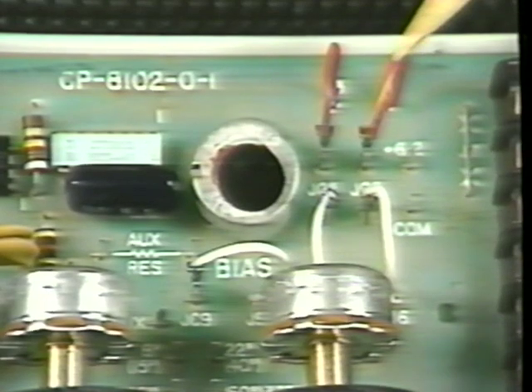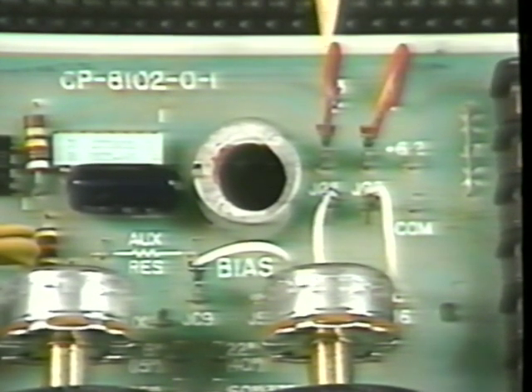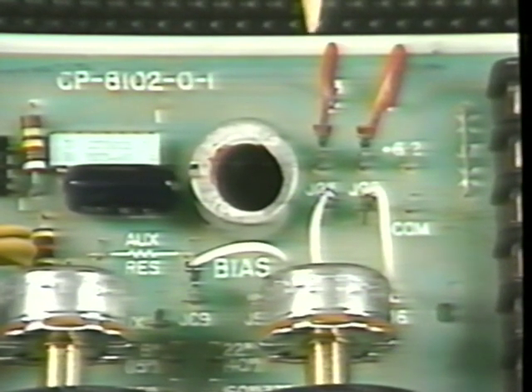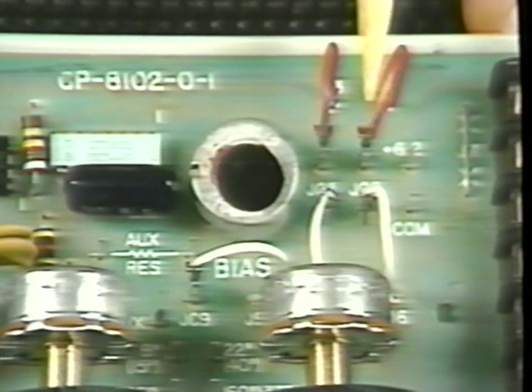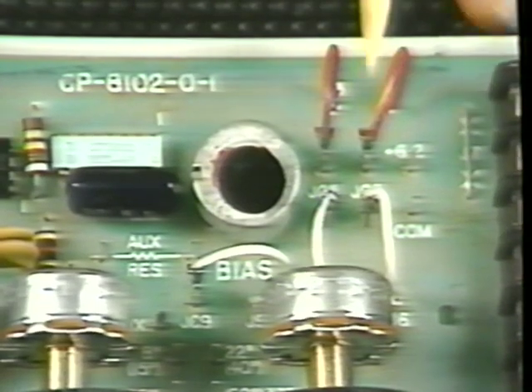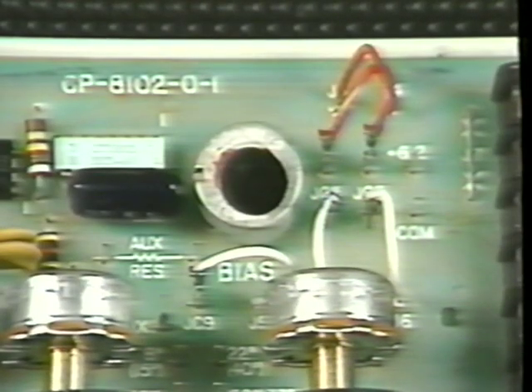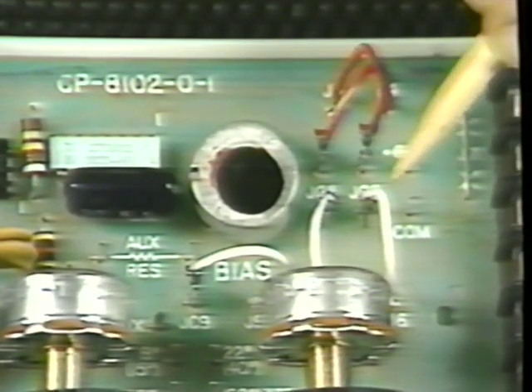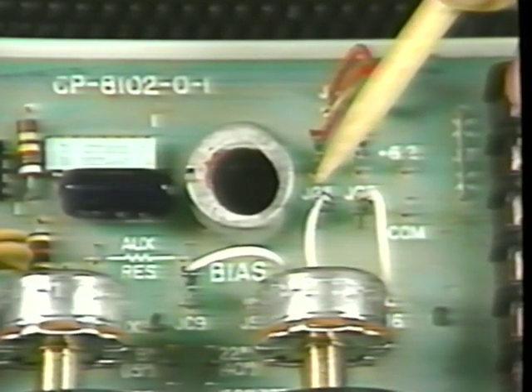The red jumpers determine the action of the controller. When they are parallel, as they are here, the controller is direct acting. By removing those jumpers from their pins and crossing them, the controller is made reverse acting. The second set of jumpers, in combination with the first, determine the reset of the controller. Remember, if bridge B has been disabled, all reset functions are also disabled, so these jumpers serve no function at that time.